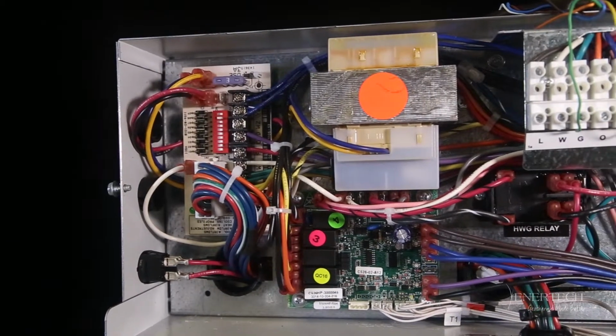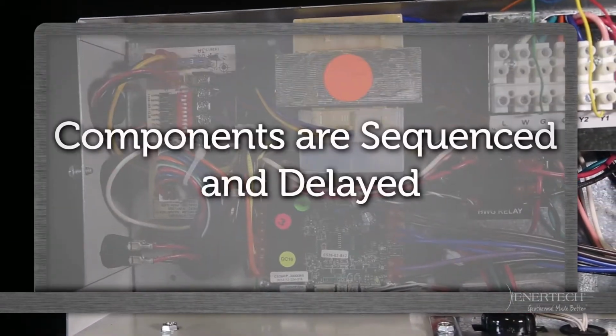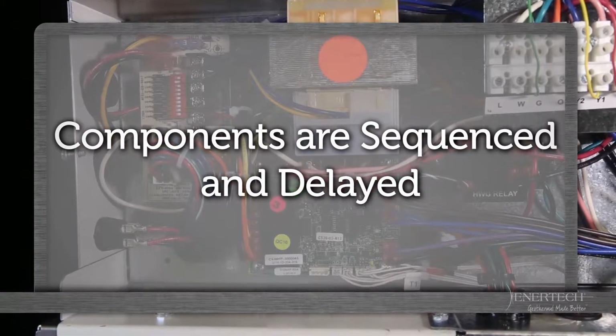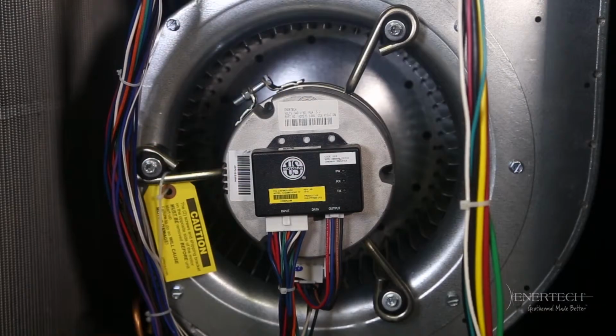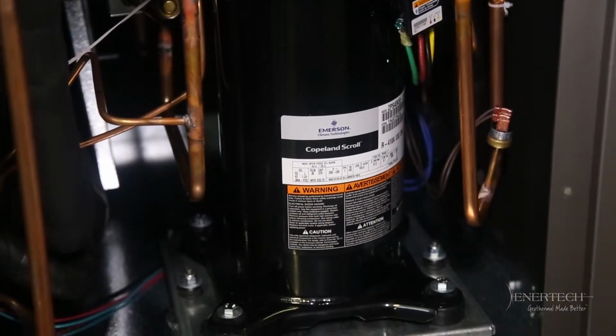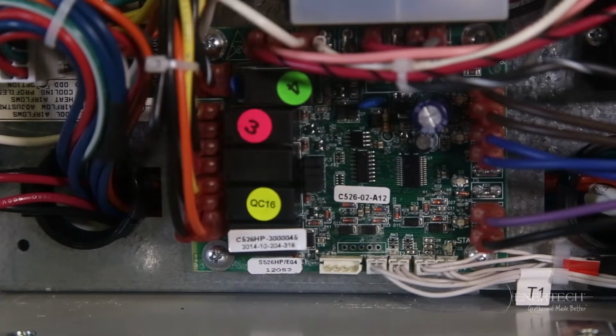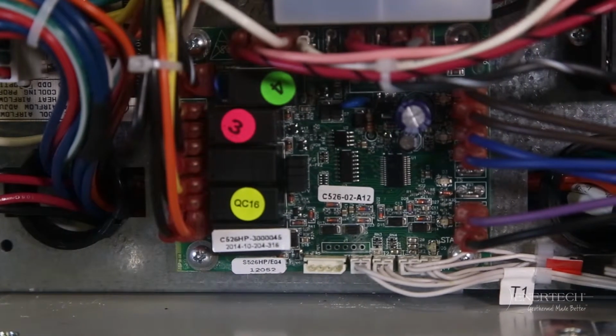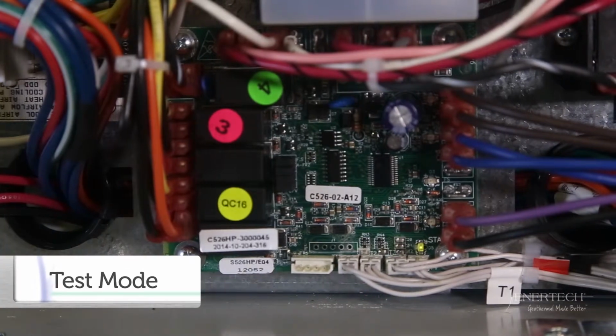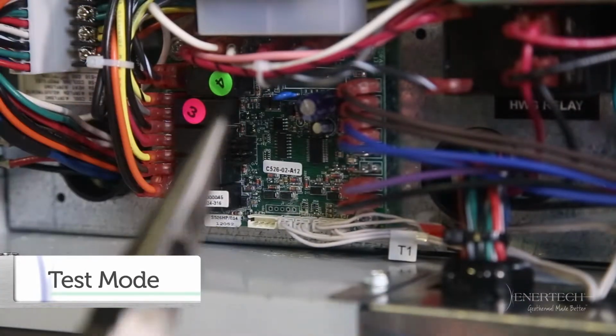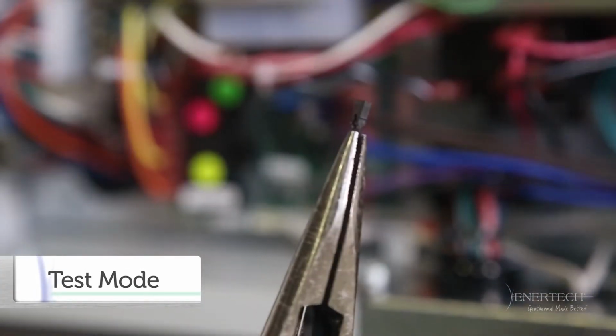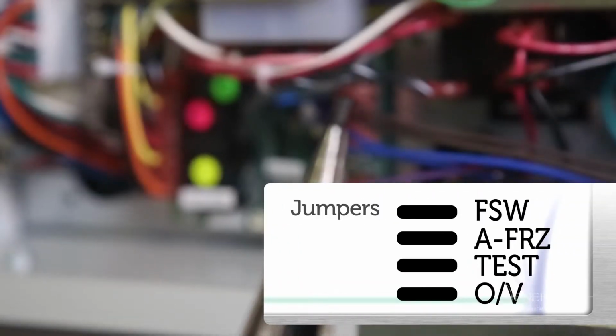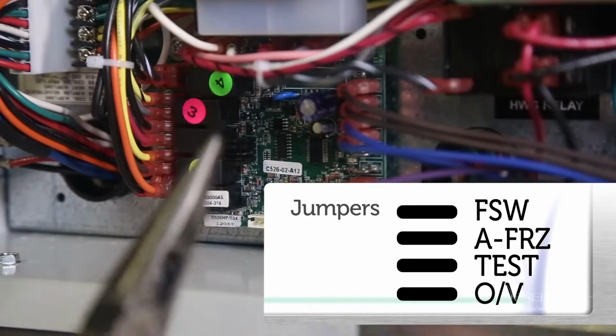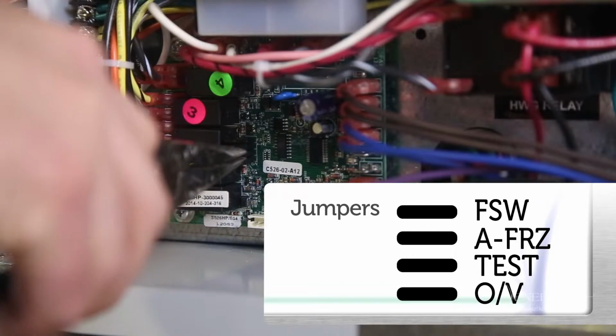Built into the board are timers. Components are sequenced and delayed for optimum space conditioning performance and to make any startup noise less noticeable. For example, there is a short delay between the blower motor and the compressor startup. The microprocessor control allows the technician to shorten timing delays for faster diagnostics by removing the test jumper located on the lockout board. It should be reinstalled for normal operation after testing. The status LED will not be illuminated during the test mode.